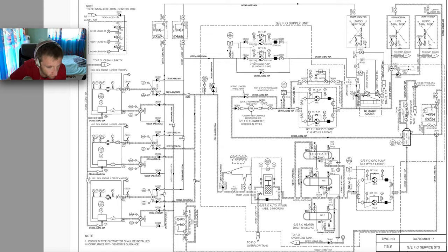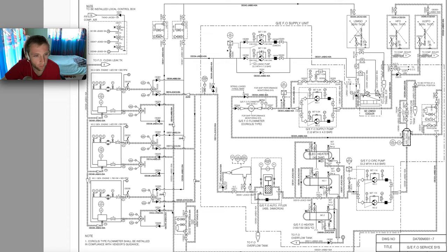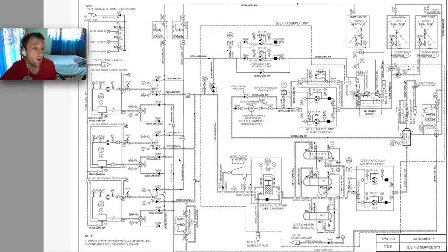We can see our fuel enters here — this is our number one diesel generator. The fuel enters from here at the inlet valve, passing through the duplex fine filters. We have a pressure indication allowance here, and then the fuel will pass through this leakage box, then out again with a flexible hose. We can see also the outlet valves — there is an automatic outlet valve controlled from the engine control room. The fuel then goes to this line and everything returns back to the fuel return pipe. This is how our diesel generators initially operate.